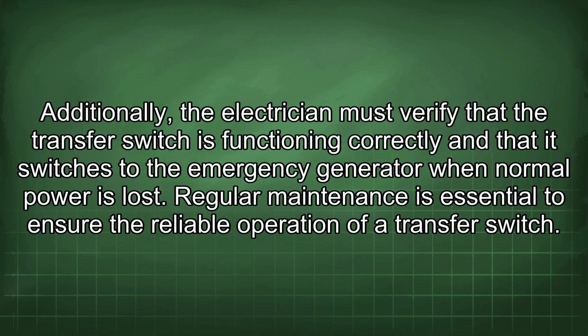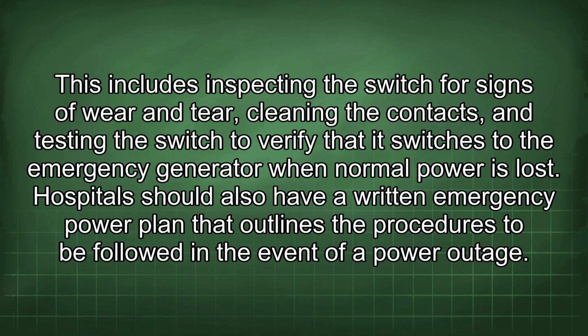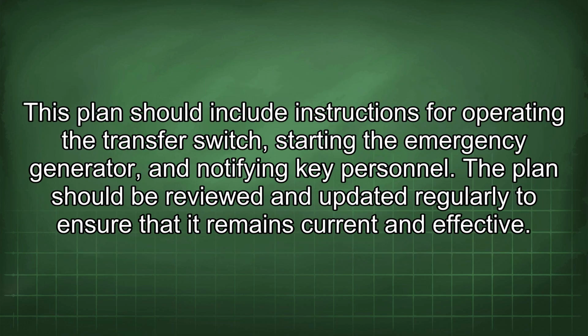Regular maintenance is essential to ensure the reliable operation of a transfer switch. This includes inspecting the switch for signs of wear and tear, cleaning the contacts, and testing the switch to verify that it switches to the emergency generator when normal power is lost. Hospitals should also have a written emergency power plan that outlines the procedures to be followed in the event of a power outage. This plan should include instructions for operating the transfer switch, starting the emergency generator, and notifying key personnel. The plan should be reviewed and updated regularly to ensure that it remains current and effective.